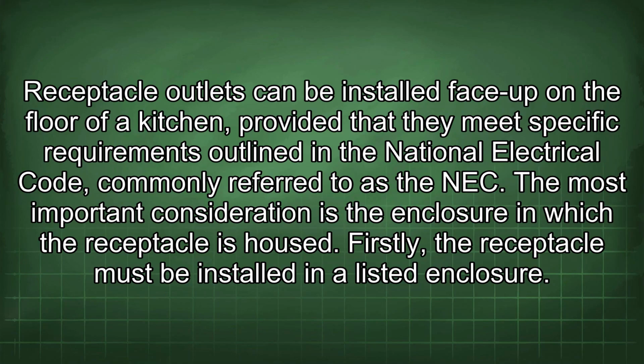Receptacle outlets can be installed face up on the floor of a kitchen, provided that they meet specific requirements outlined in the National Electrical Code, commonly referred to as the NEC. The most important consideration is the enclosure in which the receptacle is housed. Firstly, the receptacle must be installed in a listed enclosure.